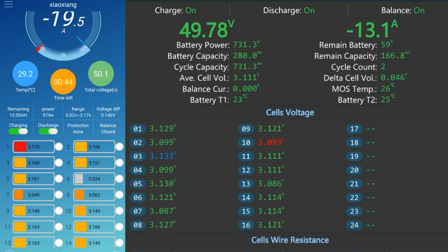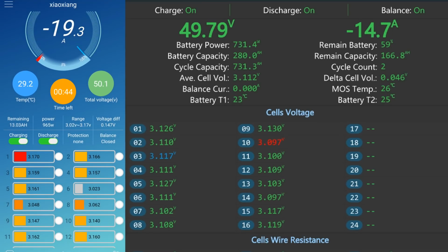So now we can already see we have a little bit of a split here. The QUCC battery is actually delivering more power than the JK-BMS battery. We've got 5 amps of difference now between the two batteries. And this is most likely because the new battery, the JK-BMS battery, is on a lower state of charge now. Okay, we are down to 12 ampere hours, 20 amps from the QUCC, 13 amps from the JK.